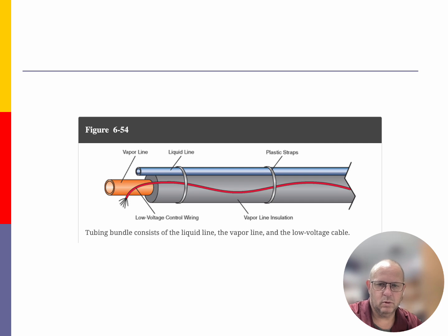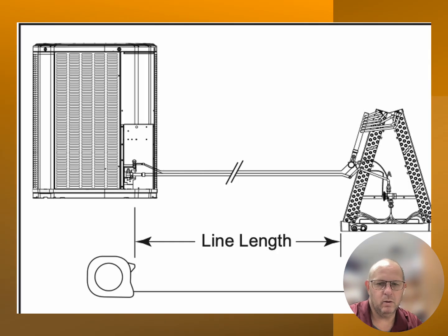So when we talk about line length, or length of line from the indoor unit to the outdoor unit, we're going to want to measure. At some point, we're going to have to add some refrigerant to this system if our line goes over a certain amount of allowable. Every system's different. Read the manuals, and then you'll understand what you need to do with the line set for that particular one.